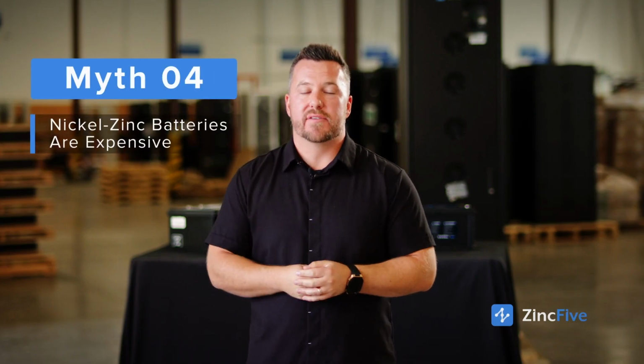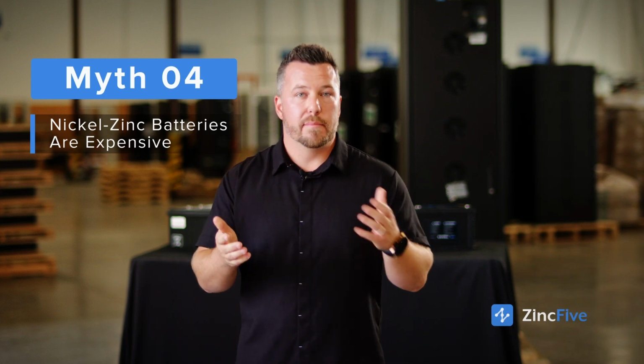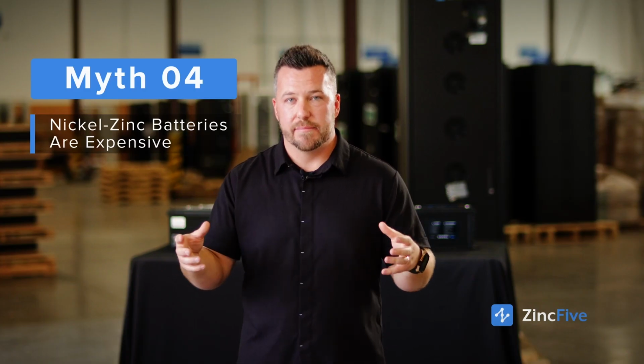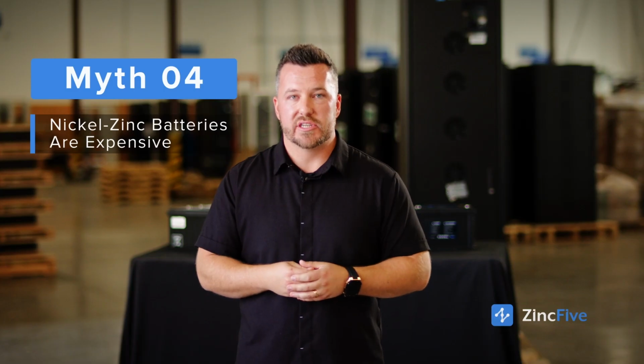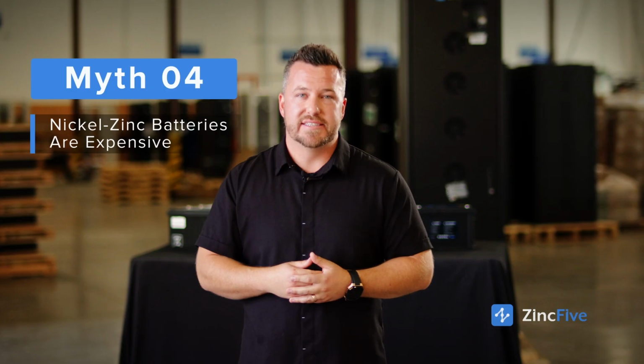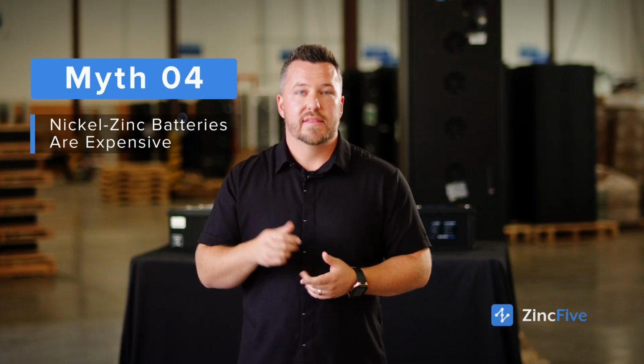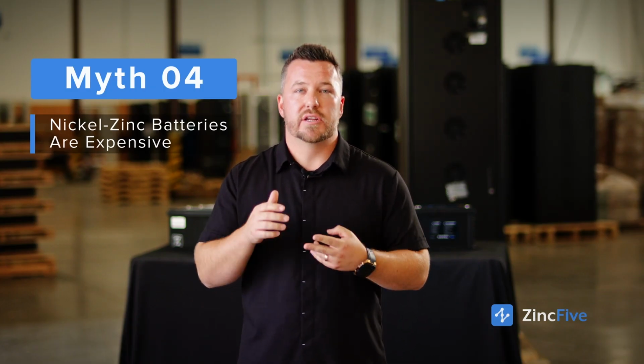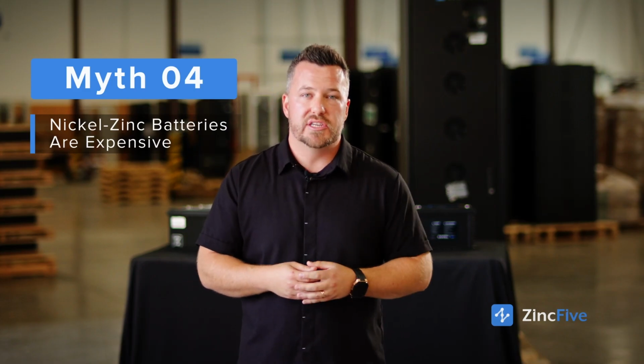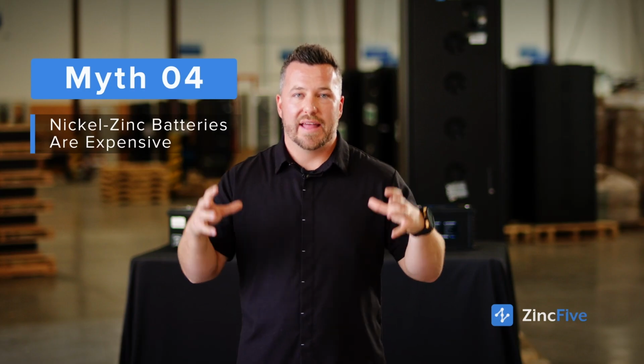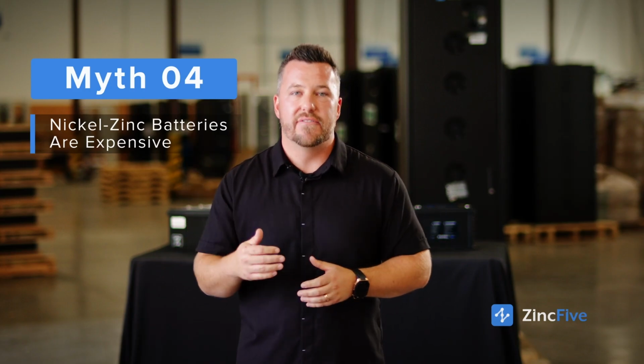The last myth I want to talk about today is that Nickel-Zinc batteries are expensive. Battery cabinet per battery cabinet, there is a cost delta. But when you step back and look at the UPS as a system, we typically require half the quantity of cabinets versus competing technologies. That means footprint savings and fewer cabinets being purchased, which improves that cost delta immediately. Coupled with the safety benefits—no fire suppression, burn-rated walls, or other codes, standards, and permitting issues with lithium and other technologies—the total cost of ownership at the system level for Nickel-Zinc is significantly less.